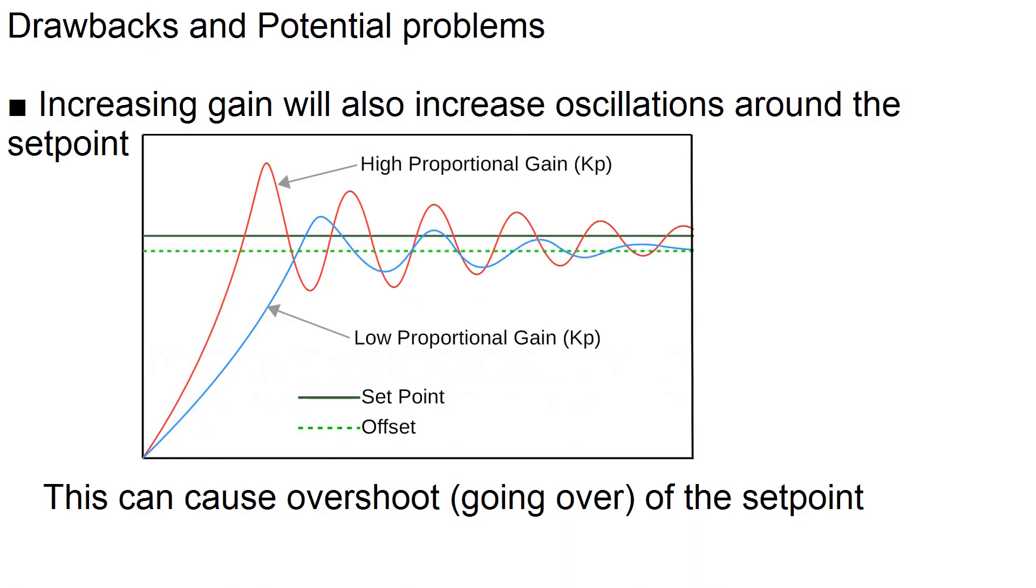Now, the other thing is, increasing the proportional gain, as you saw, caused it to react faster, but it could also cause it to overshoot the target temperature and then start oscillating, that is, go above and then below and keep repeating that pattern over and over again. If the proportional gain is too low, it may actually never get to the set point, or it'll just come up really slowly.